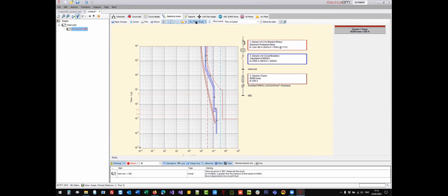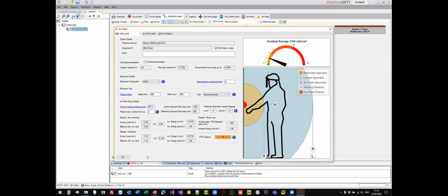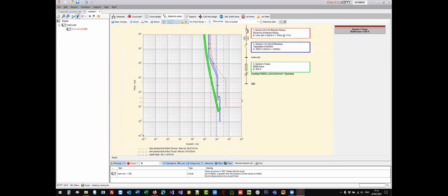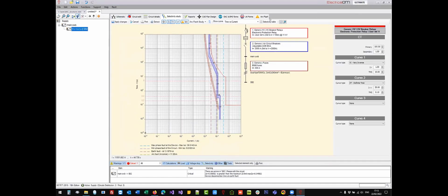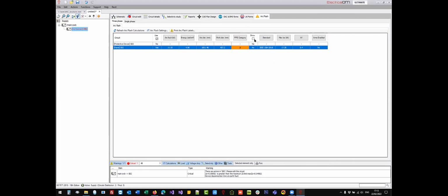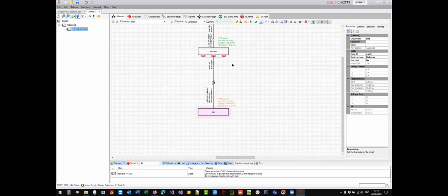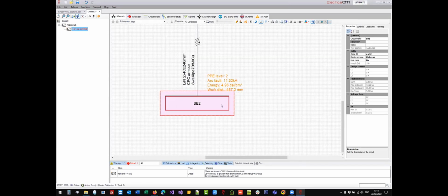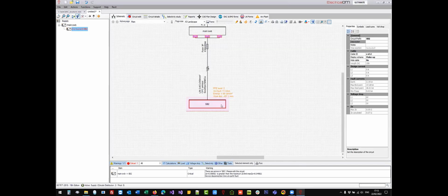And now if we perform the arc flash study on the panel, we can see that we get the relevant PPE category based on the device used to protect this panel, which is the BS88 fuse. Okay. Now, if we go back to the arc flash module, we can select this and choose to show. So we can include this PPE category to this panel as well.